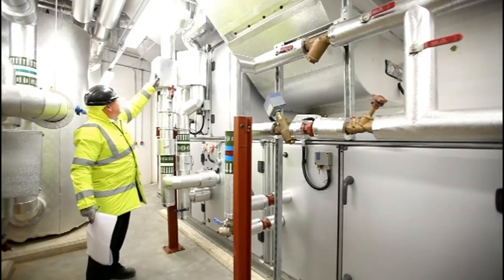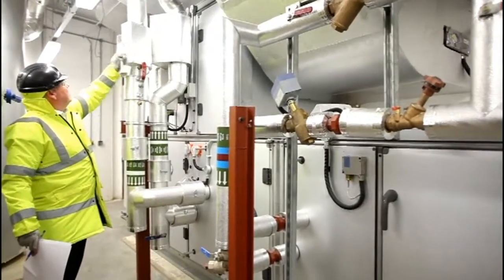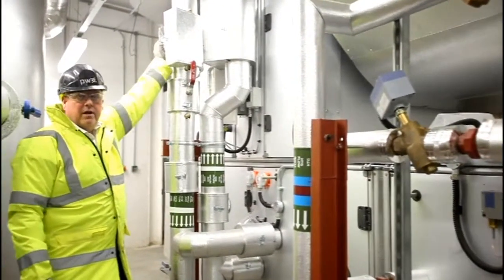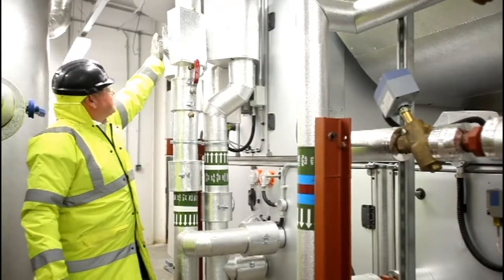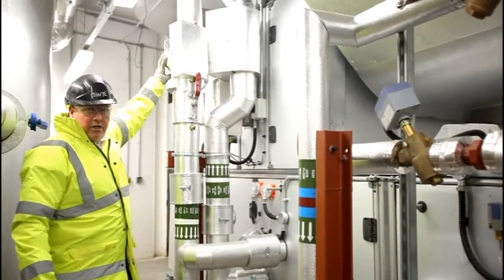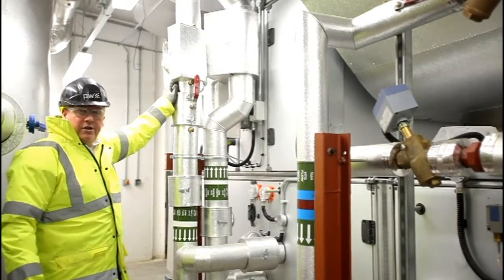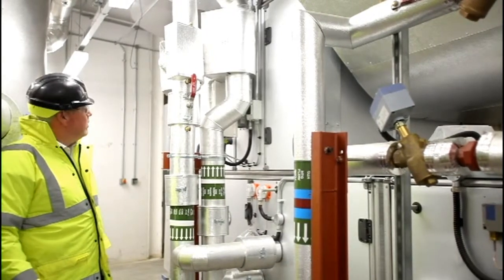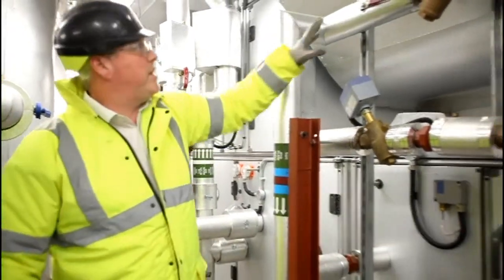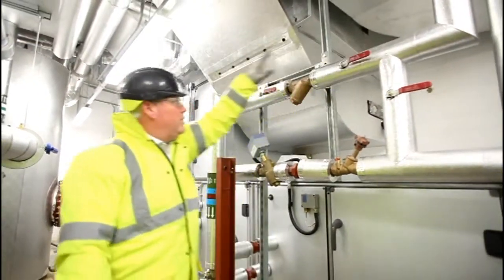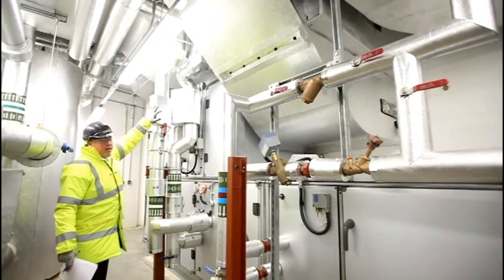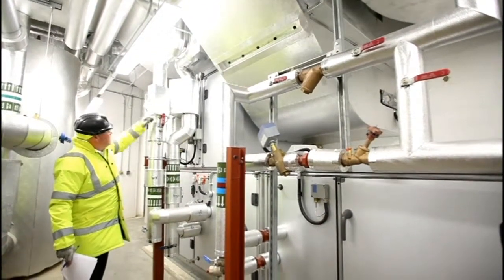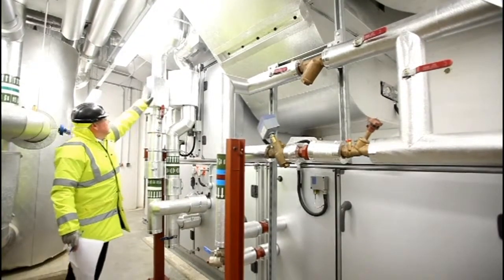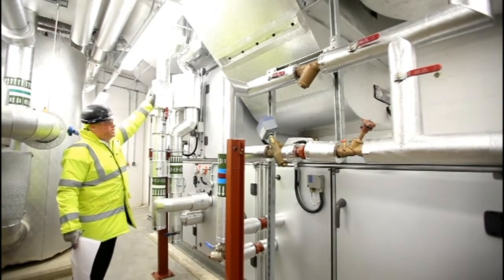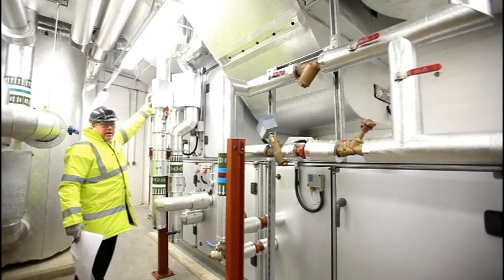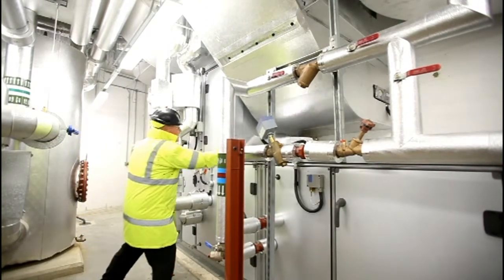Very easily take the valve cover off, get to the valve, take off the insulation and operate the valve. This is because we need to vapour seal the chilled. If we don't vapour seal the chilled, we get what we call condensation, and we get lots of water dripping on it. So on the heating, the valves are very clear. On the cooling, you'll get a valve box. In some instances, you will get a handle protruding. Other instances, you will get a valve box. Disconnect the valve box, go into the valve, turn the valve.